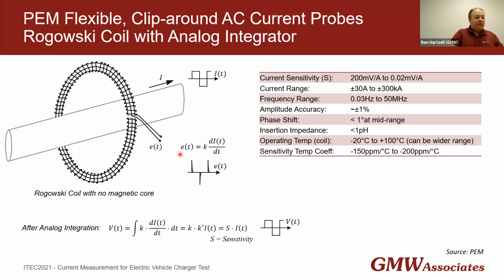If the coil has a constant cross-section and evenly spaced number of turns, the induced voltage is proportional to the rate of change of the primary current, di/dt. And here we have a very simple plot of the induced voltage. After analog integration, we have the sensitivity times I, the primary current, gives us a voltage output waveform proportional to the current waveform.